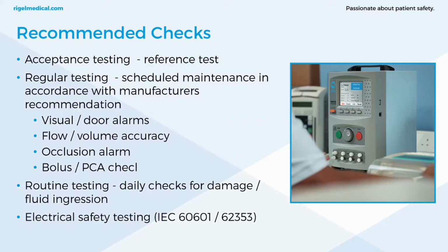So the recommended checks: we've got acceptance testing or reference test, not normally as comprehensive as the regular tests, but you'll often have a quick flow rate or volume check, and also a quick check of the occlusion. So this will always be recommended by the manufacturer.